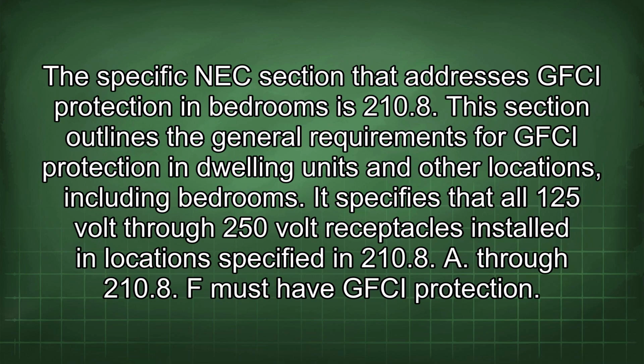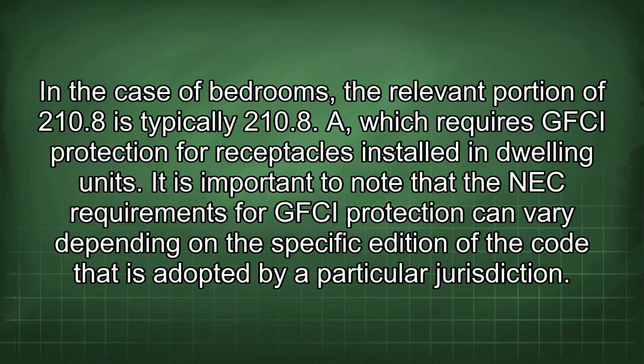The specific NEC section that addresses GFCI protection in bedrooms is 210.8. This section outlines the general requirements for GFCI protection in dwelling units and other locations, including bedrooms. It specifies that all 125 volt through 250 volt receptacles installed in locations specified in 210.8 A through 210.8 F must have GFCI protection. In the case of bedrooms, the relevant portion of 210.8 is typically 210.8 A, which requires GFCI protection for receptacles installed in dwelling units.